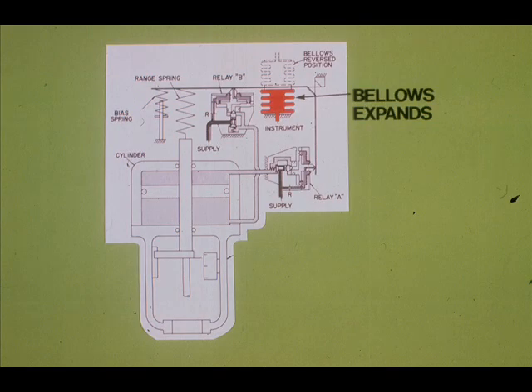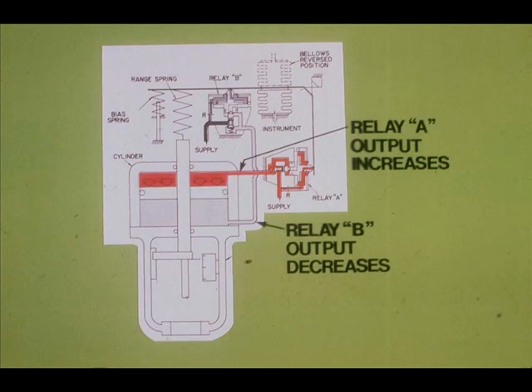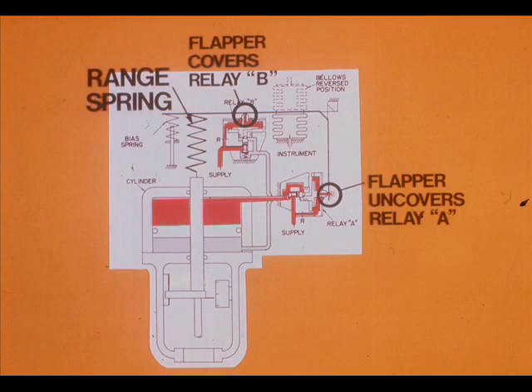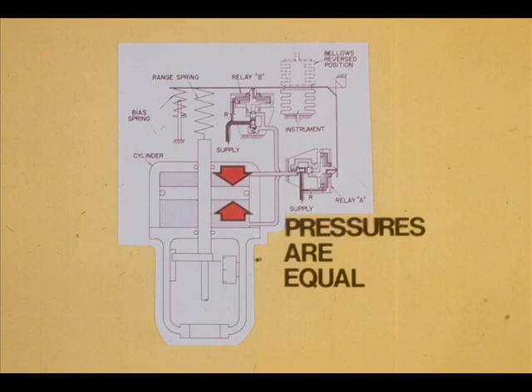We will now consider the Fisher 3570 positioner operating sequence. Assume that the instrument signal increases: the bellows expands, a flapper covers relay B nozzle, and a flapper uncovers relay A nozzle. Relay B output decreases; relay A output increases. The piston is forced downward until the range spring pulls the flapper against relay B and away from relay A. Relay B then increases output and relay A decreases output. When rebalanced, the pressure on both sides of the piston are approximately equal.